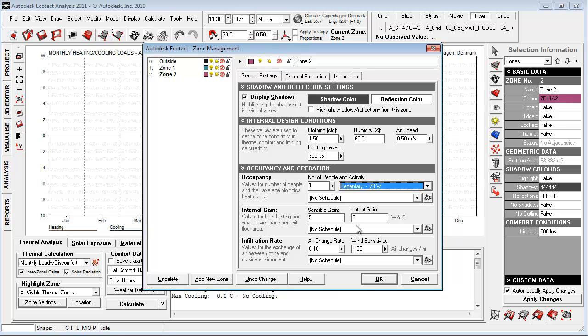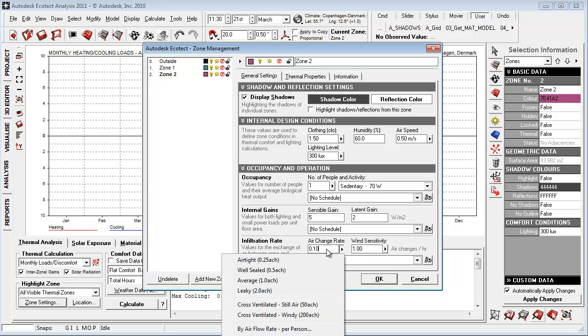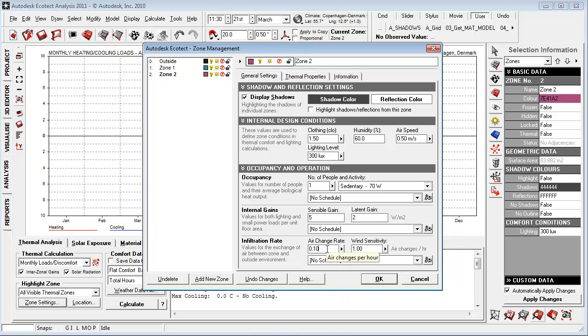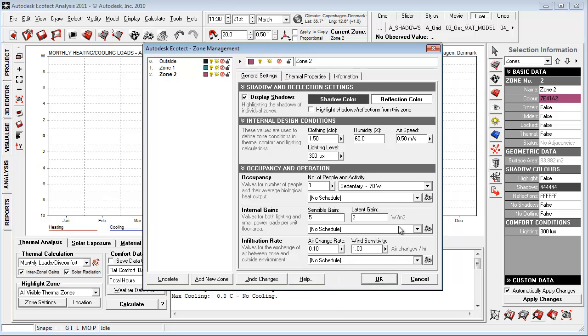Sensible gains, latent gains, and of course, the infiltration rate and wind sensitivity, which is very important because Ecotect is using wind-dependent infiltration in the calculation of heating and cooling loads. Let's set this to 0.1, which is the demand in Denmark. And let's start out setting it to very sensitive.